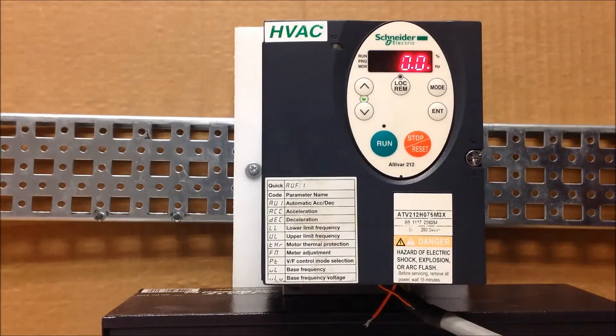This video will show you how to program reference switching functionality on the ATV212 drive. When we're talking about reference switching, we're talking about switching your reference channels, meaning your speed channels, not your command. Your command is going to still stay the same as whatever that CNOD parameter is programmed at, which is your command mode selection. This is strictly reference switching in means of a speed reference.